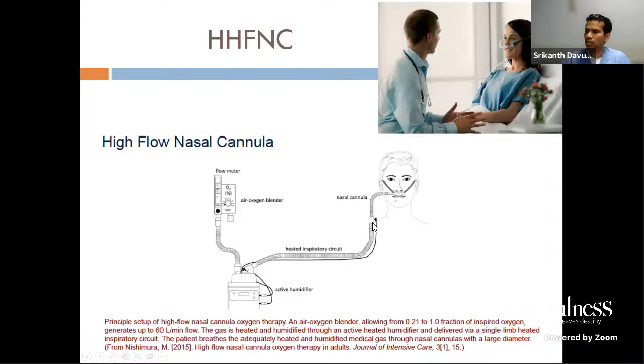So what is this? Here, if you see in this picture, you take oxygen through a flow meter, and you have an oxygen blender where you can set the FiO2 that is added to the flow. Usually heated humidified oxygen systems can give from 10 liters all the way up to 60 liters. You can adjust the FiO2 from 21 all the way up to 100. This oxygen goes through the humidification system and then through the interface to the patient. The interface has a heated circuit that prevents condensation.